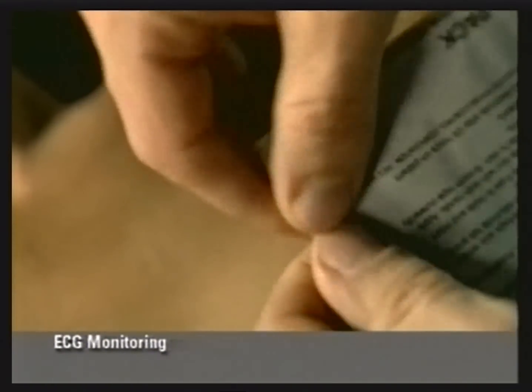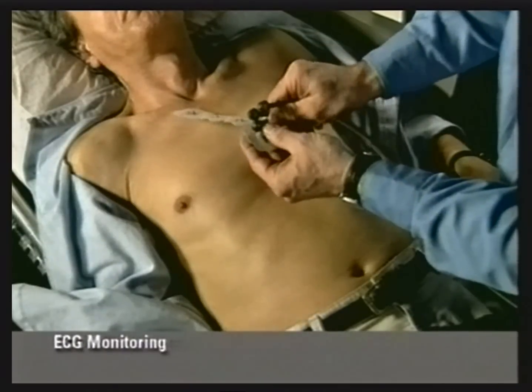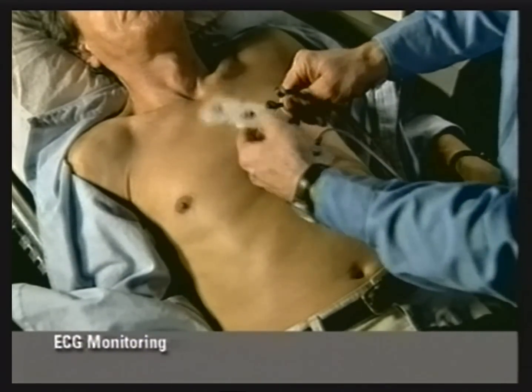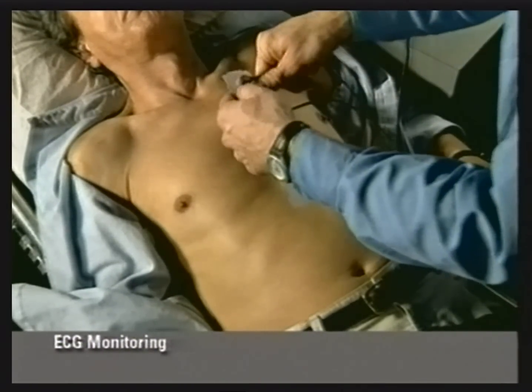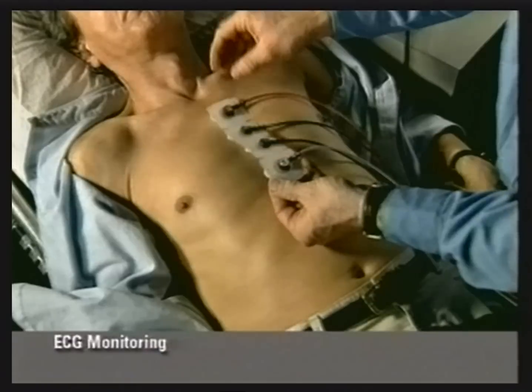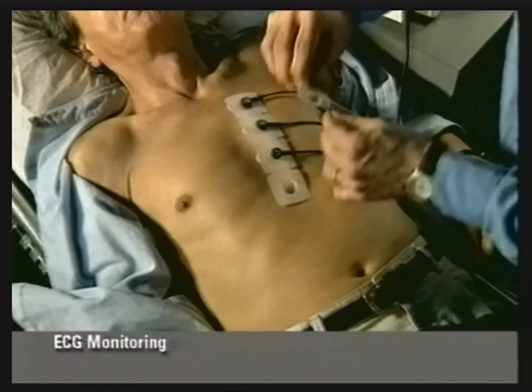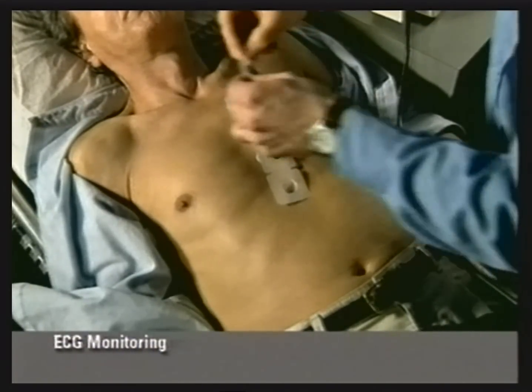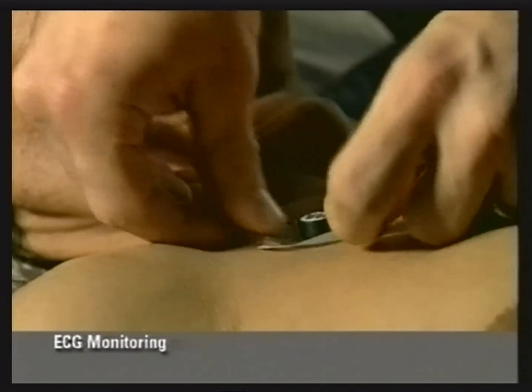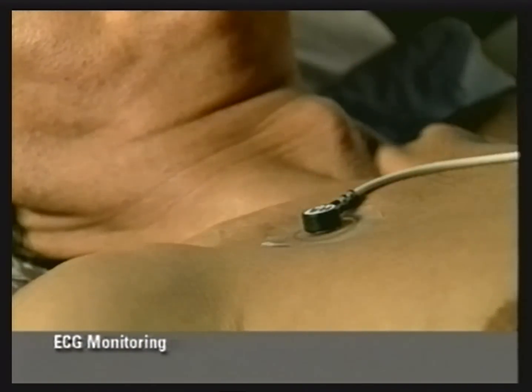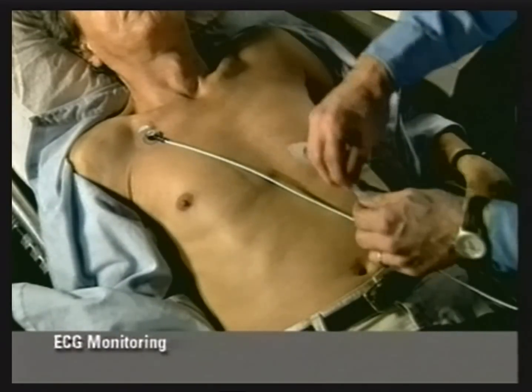Confirm that the electrode's expiration date is not passed, and attach an electrode to each of the lead wires. Remove the electrode from the carrier and check that the gel is intact. Holding the electrode taut with both hands, apply the electrode flat to the skin. Avoid pressing the center of the electrode.